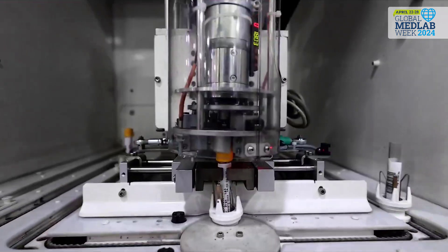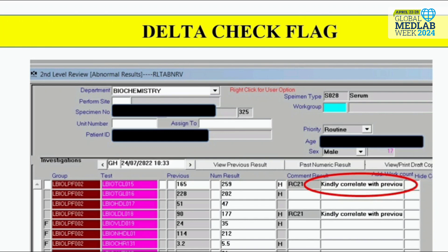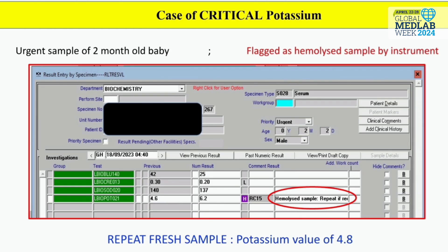To assure error-free results, all tests are subjected to three major checkpoints. The first is the use of artificial intelligence, which stops the test in case of a QC failure. The delta check module is inbuilt, which compares the result with the previous value of the patient. The micro-sensors for HIL indices check for hemolysis, icterus, and lipemic interferences, and put a comment on the report.